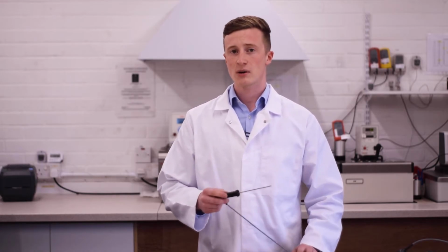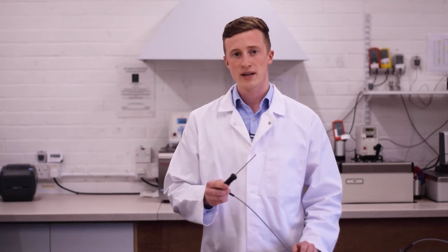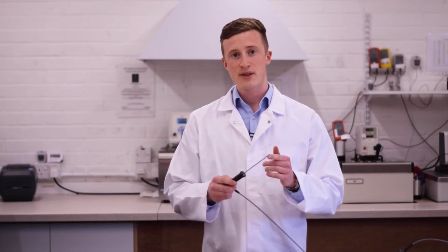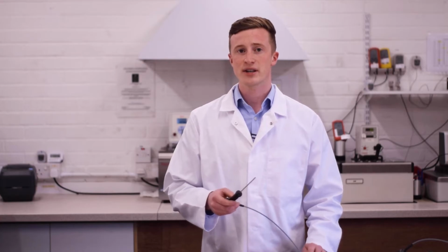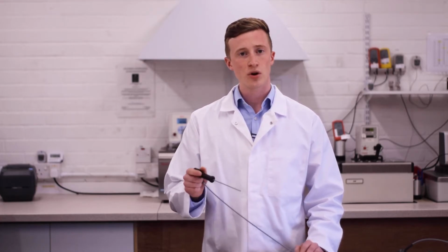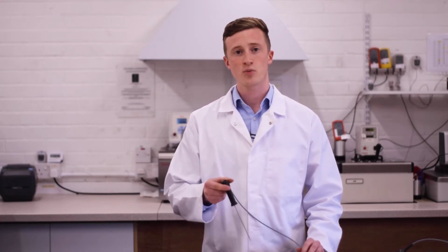It's important to note, however, that you should not get air sensors wet due to the exposed sensor, and this includes steam and condensation. Likewise, do not use air sensors for probing physical product, as this will damage the sensor.